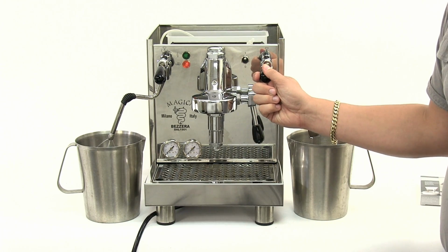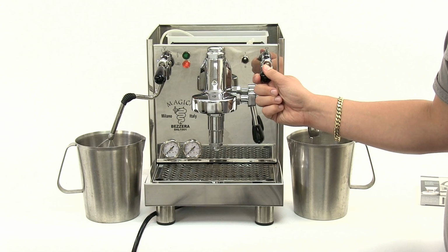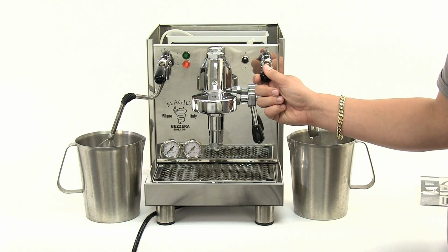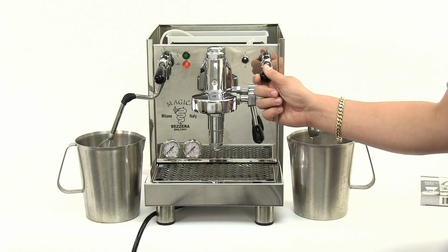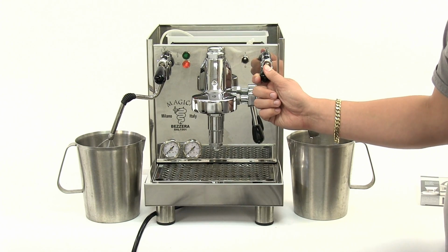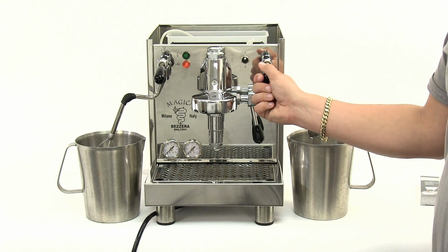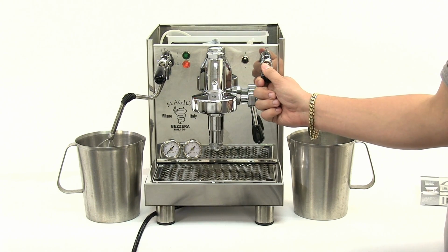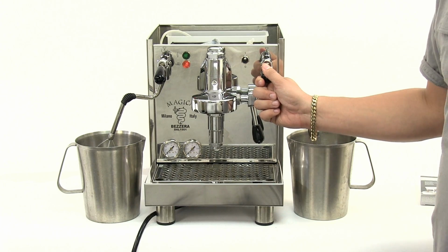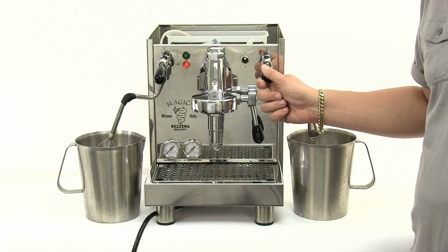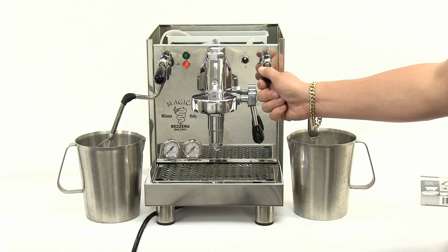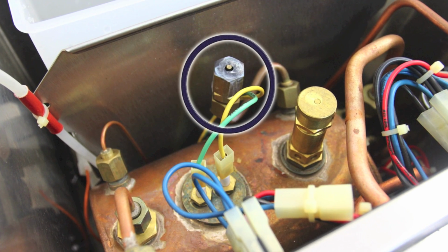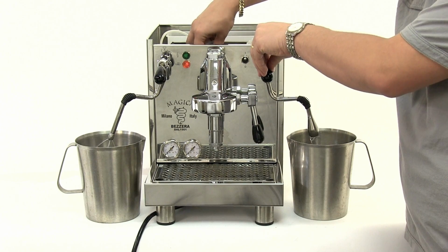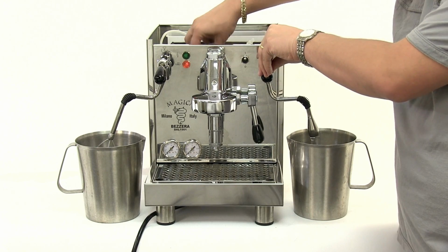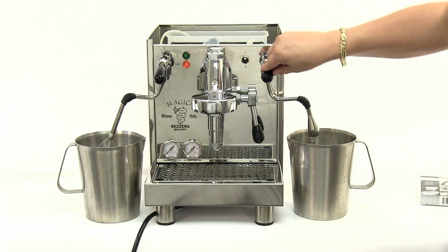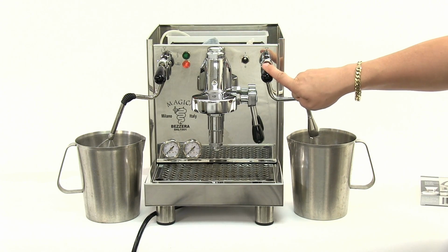So you can see the boiler's filled all the way and the water's coming out both sides. If you want to hurry the flow on your steam side, you can also remove the tip. I didn't do that. I'll give you one more word of caution: you may get a little bit of water coming out of your vacuum breaker valve because, again, the boiler is overfilled and the vacuum breaker valve is at the top. So what you can do is just wrap a towel or a small cloth around the vacuum breaker valve in order to solve that issue.